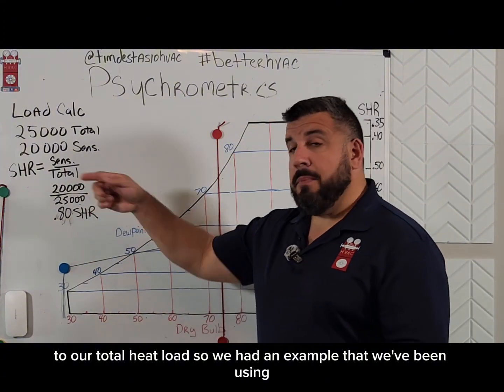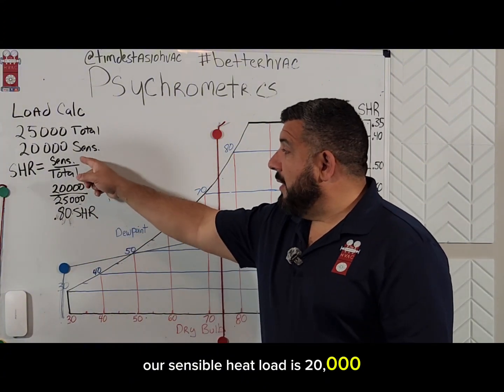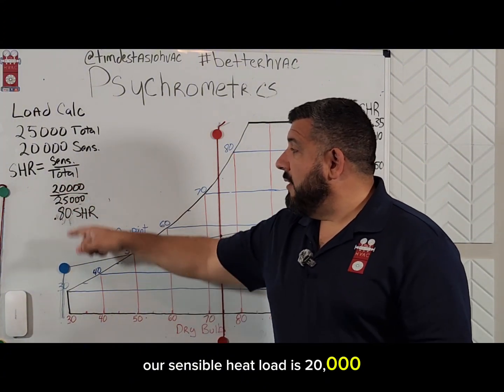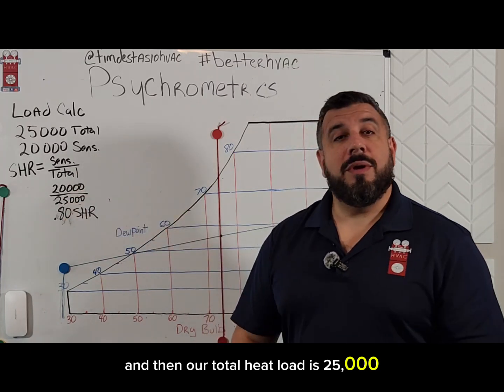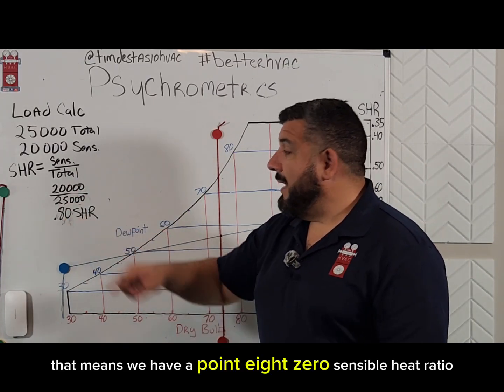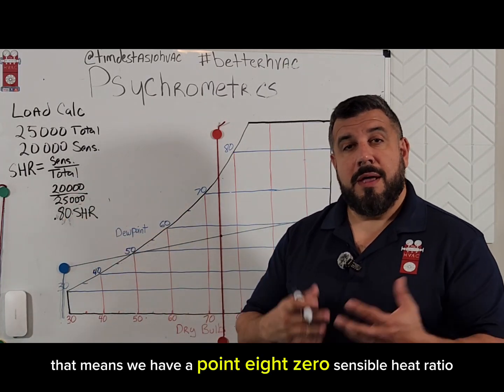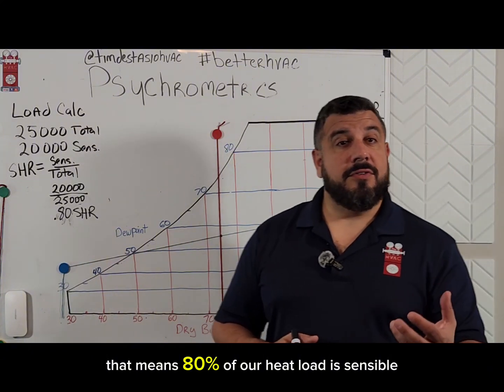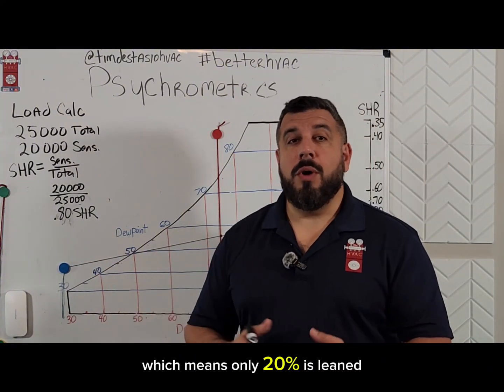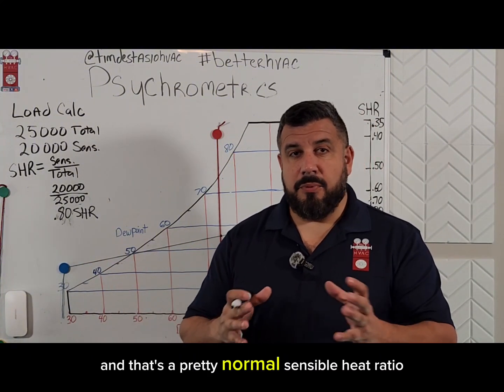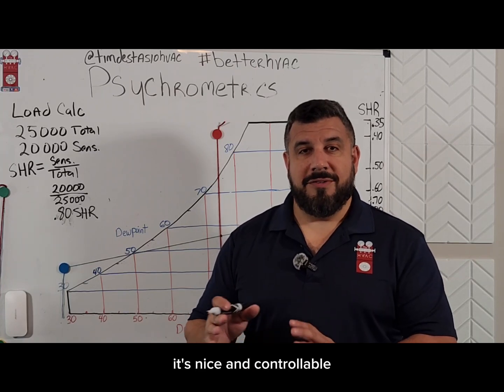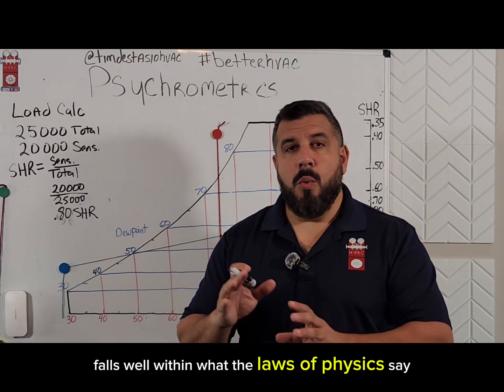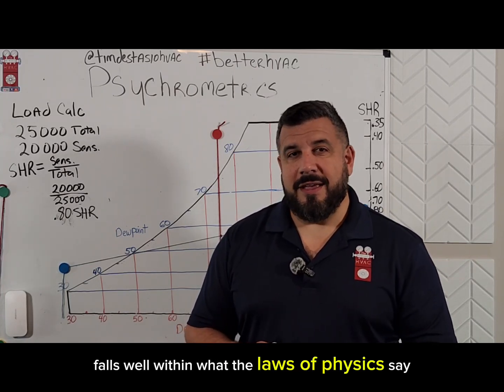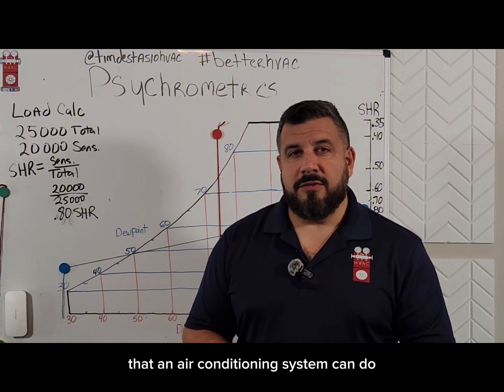So we had an example that we've been using. Our sensible heat load is 20,000, and then our total heat load is 25,000. That means we have a 0.80 sensible heat ratio. That means 80% of our heat load is sensible, which means only 20% is latent. And that's a pretty normal sensible heat ratio. It's nice and controllable, falls well within what the laws of physics say that an air conditioning system can do.